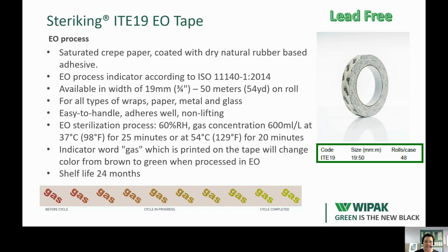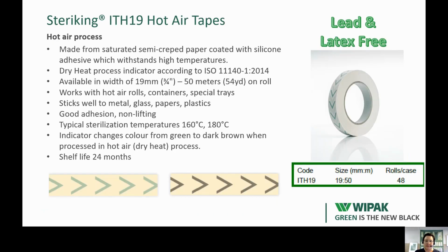So the indicator in this tape is in this kind of gas text format, not the stripes like what we have in many other tapes. And that is turning color from brown to green when exposed to these EO sterilization conditions. And the shelf life of this tape is 24 months. Then the last tape in our range is this hot air tape that is intended for dry heat sterilization. And it's made from saturated semi-crepe paper that is coated with silicone adhesive, because that withstands the high temperatures present in this hot air sterilization process.